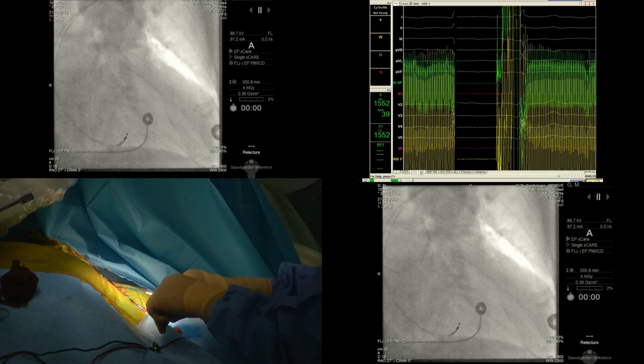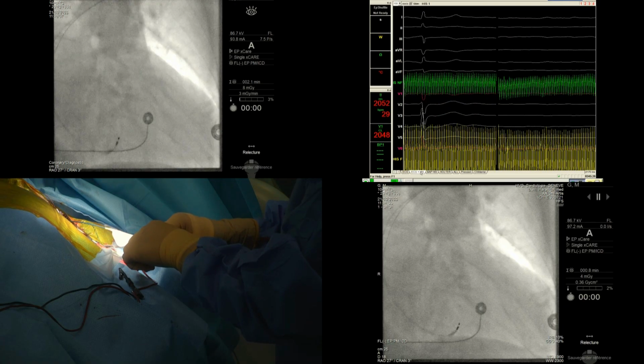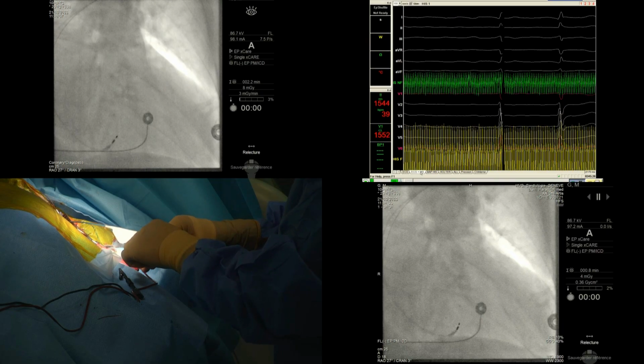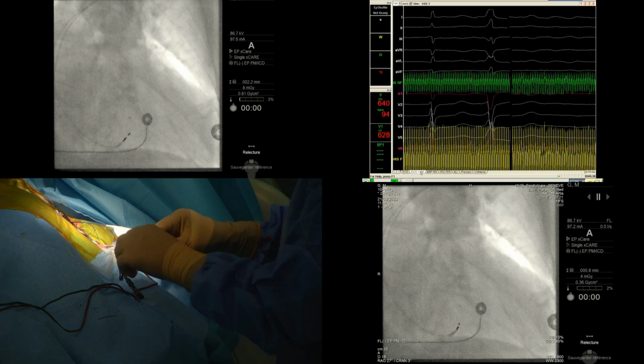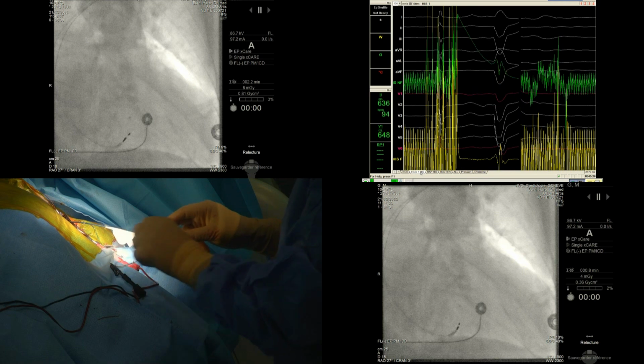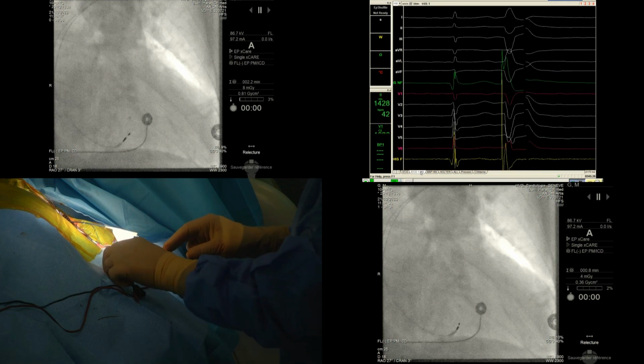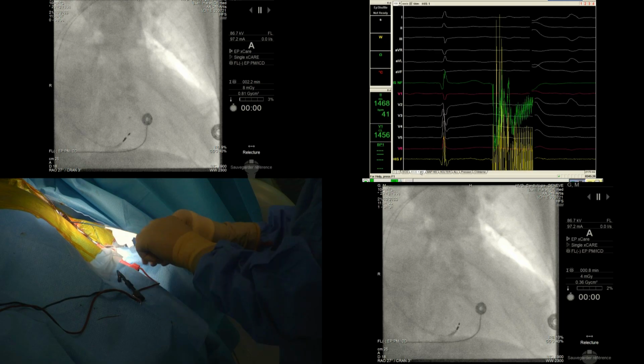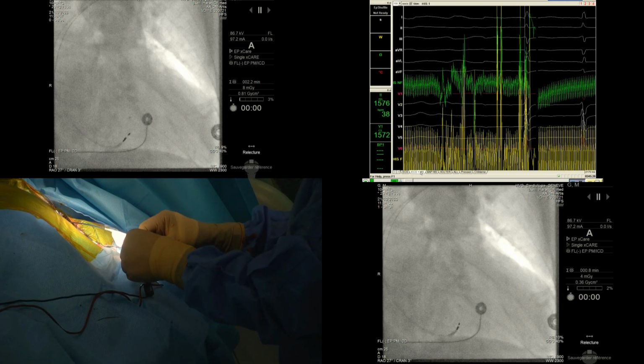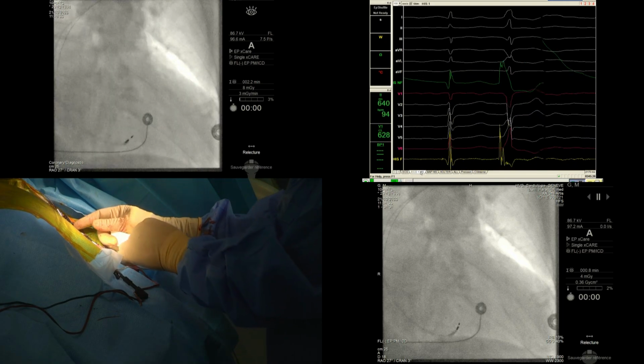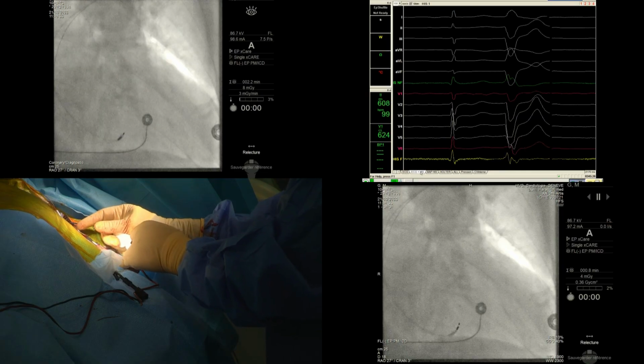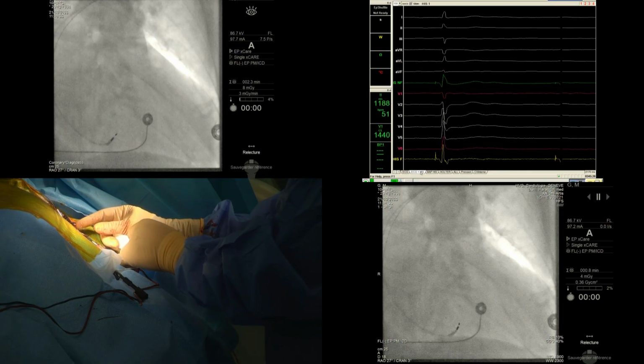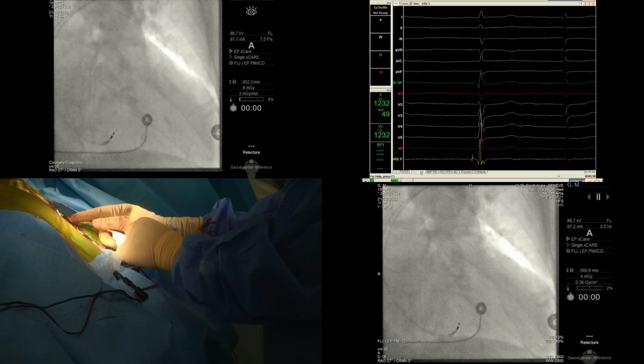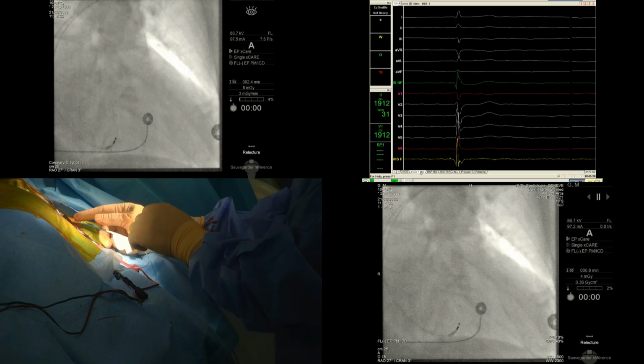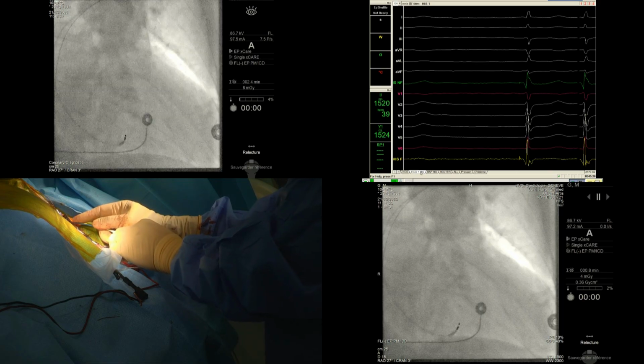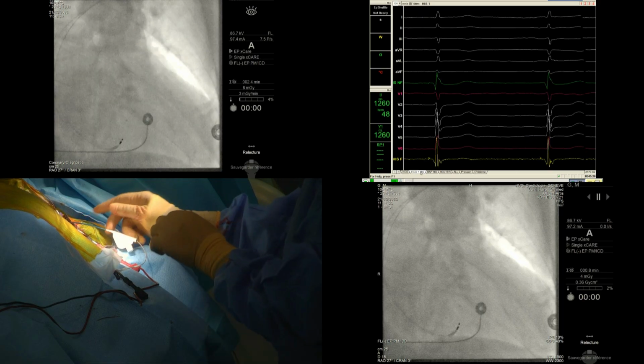After disconnecting, the lead is then fixated by rotating the lead body. Here the lead has just moved slightly, so it's reconnected, and one can no longer see the His potential. So the lead needs to be repositioned. The His bundle needs to be located again, and that's where the reference image comes in handy. So there it is, and the His lead is now stabilized in position and fixated again.